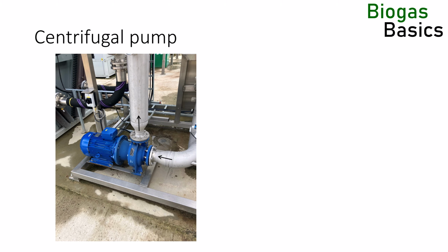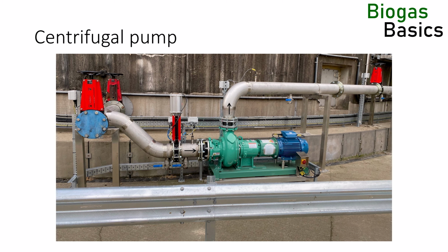Centrifugal pumps can be made self-priming by installing a non-return valve in the suction line which prevents liquid from running from the pump. But non-return valves should not be installed in substrate systems of biogas plants as they block, break or leak in digestate. The main applications for centrifugal pumps on biogas plants are in the hot water system and for drainage, though they can be an alternative to rotary lobe pumps in high-flow, low-viscosity digestate applications.